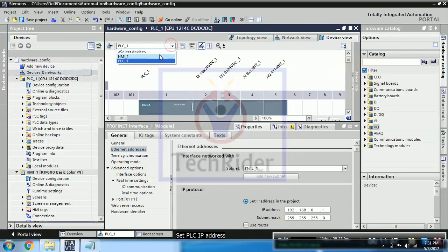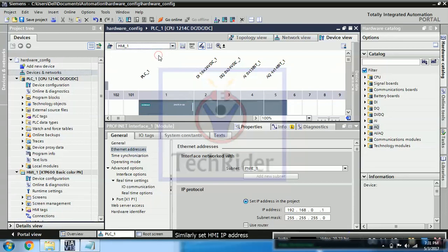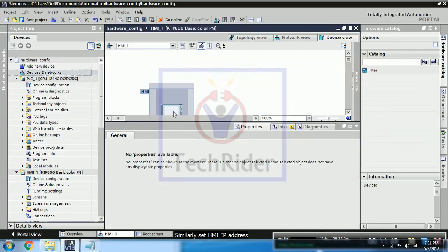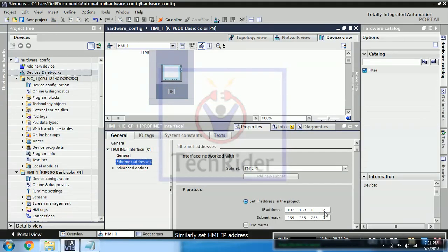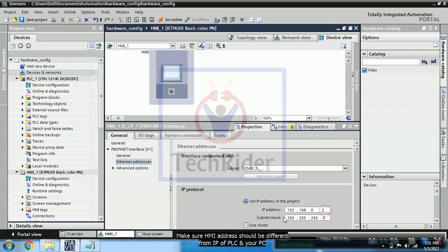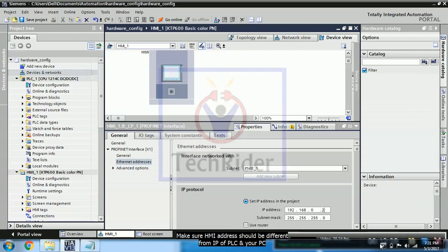And same for the HMI, you have to configure IP address which should be different from the PLC as well as your PC. And not only that, but also all the components and devices that you are going to connect should have a different IP address. Unique IP address is required.